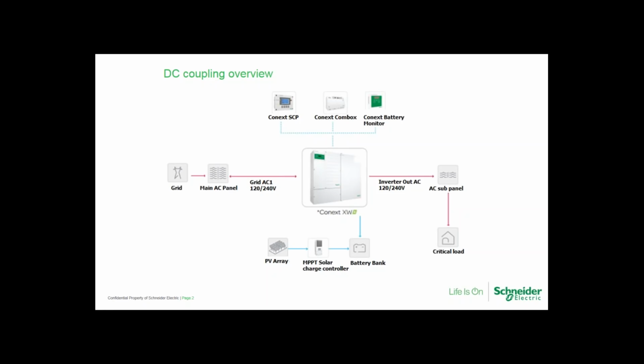So even though it is a regulator and it will regulate to the maximum charge rate, once you reach the absorption stage, the leftover current will be used to support the load. So if you add up, say you've got three 60 amp controllers, that's 180 amps. Is your battery bank sized appropriately to accept 180 amps? And that's also going to be related to the battery chemistry.